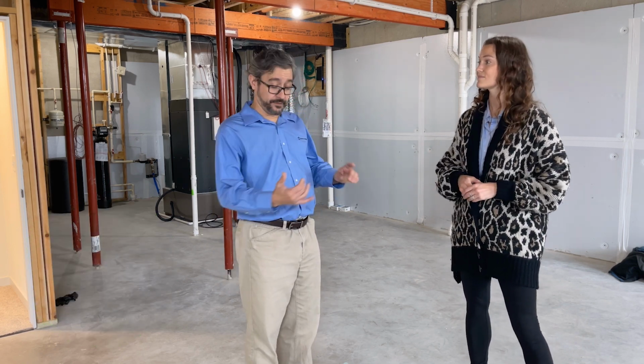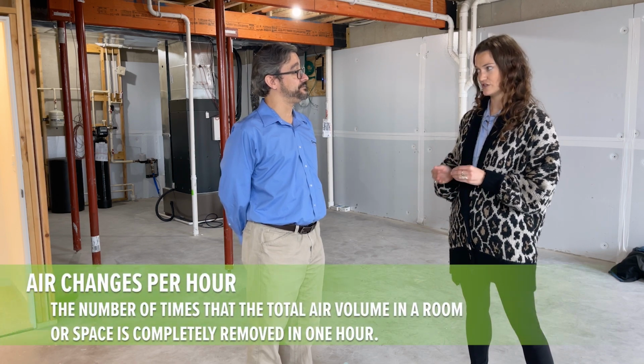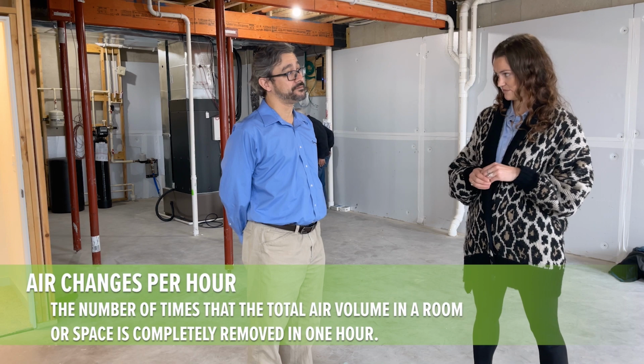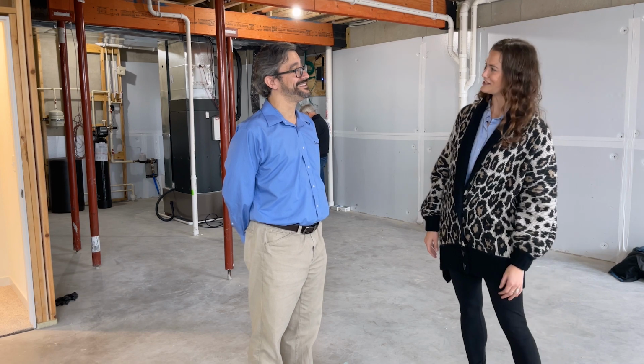And so we're looking at the blower door, vents, everything else. We're checking out just how energy efficient your home is at this present moment. Exactly. We're aiming big. I think I've said before that we really hope to hit the air changes per hour. We're looking for 1.5 air changes per hour at 50 or less. And in terms of the ducts, I'm not really sure what the metric is there, so we'll find out today. Awesome. All right, let's check in with them.